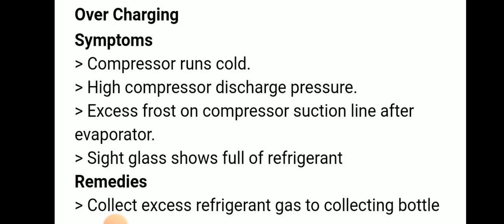Overcharging symptoms are: compressor runs cold, high compressor discharge pressure, excess frost on compressor suction line after evaporator, and sight glass shows full of refrigerant.